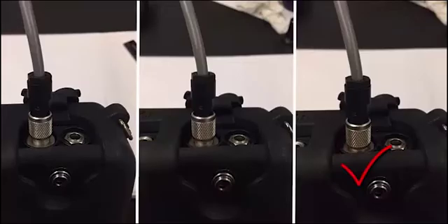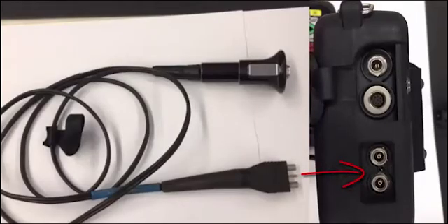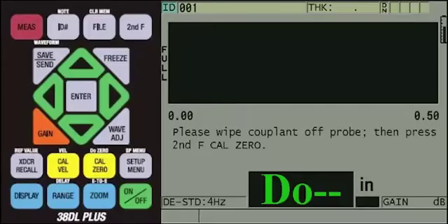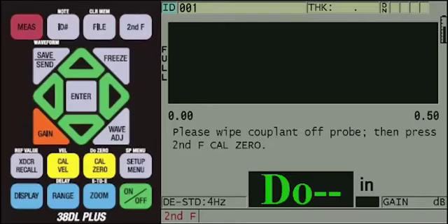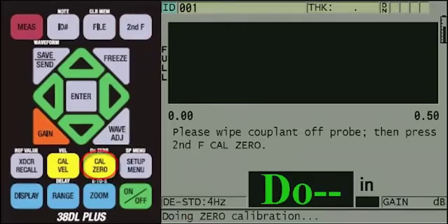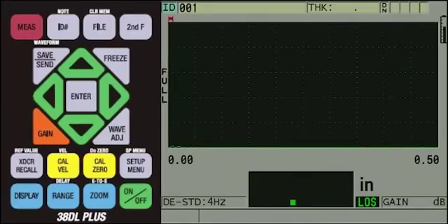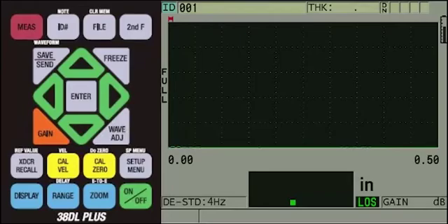We can then plug the D-790-SM transducer cable into the top of the 38DL Plus and turn the instrument on. Once the gauge powers on, it will prompt the user to perform a DO-0. Make sure there is no couplant on the end of the transducer. You can then press and release the second F key first and then press the yellow CAL-0 key. Once this process is completed, the measurement screen on the instrument will be displayed. We will use the waveform display to ensure that the D-790-SM is inserted into the B-Scan buggy in a way that provides good signals on screen.